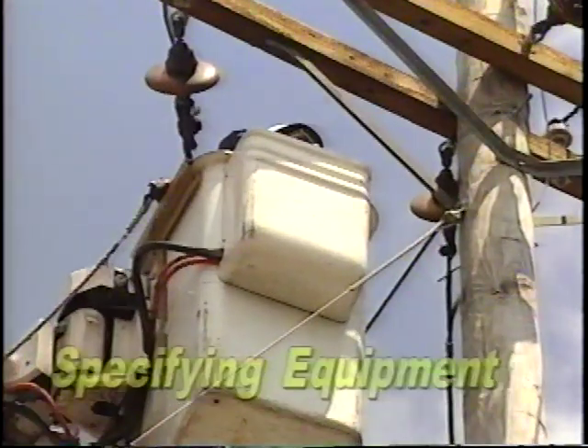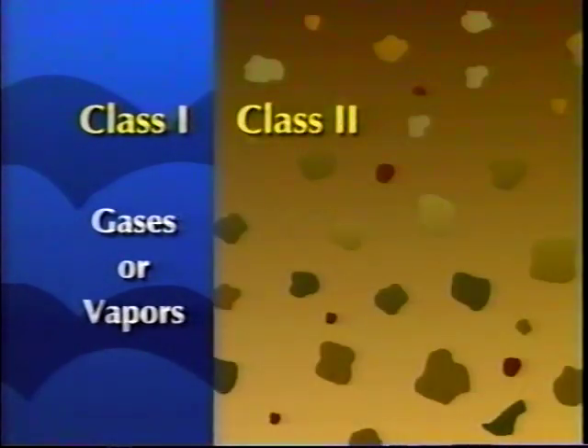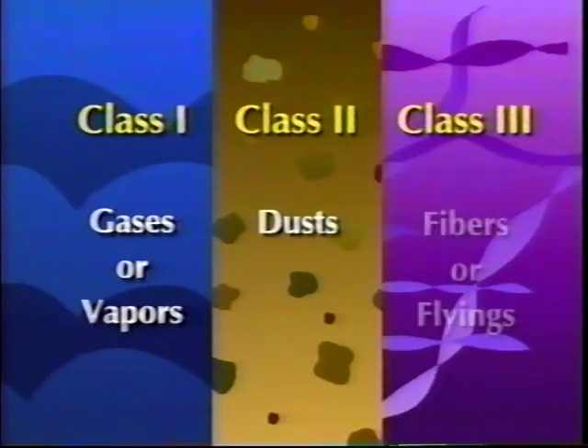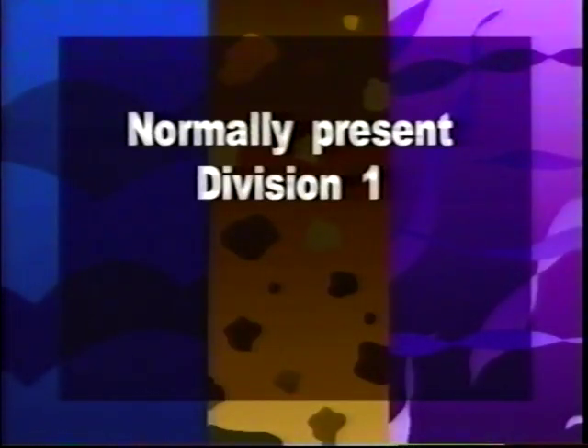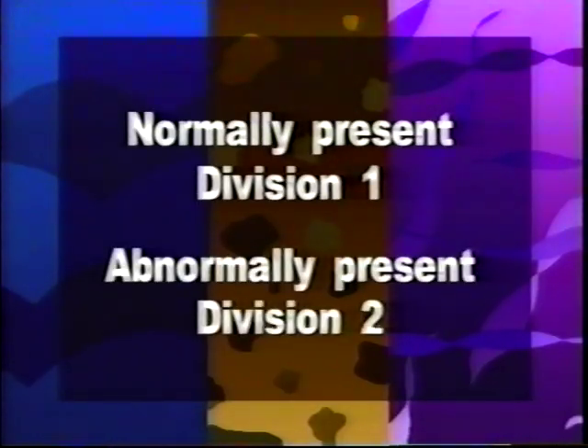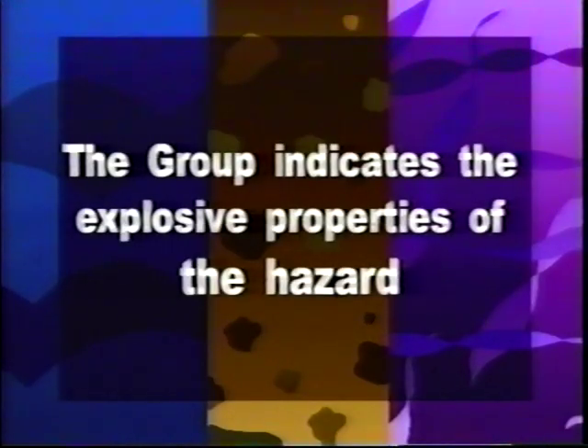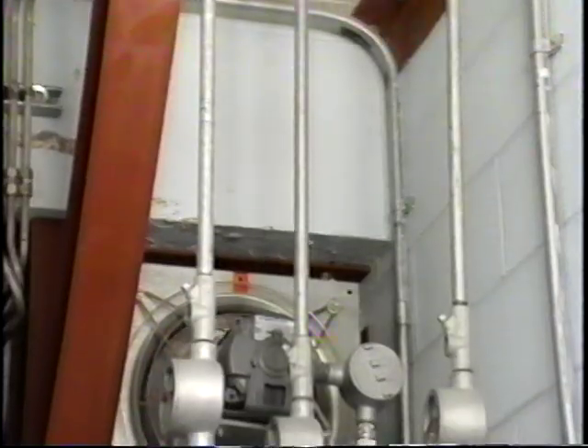Now for a quick review. If it's a gas or vapor, it's Class 1. If it's combustible dusts, it's Class 2. And if it's ignitable fibers or flyings, it's Class 3. If the atmospheres are normally present, it's Division 1. If the atmospheres are abnormally present, the area is Division 2. The group indicates the explosive properties of the hazard. If an area has more than one type of hazard, you must have equipment approved for each hazard type.